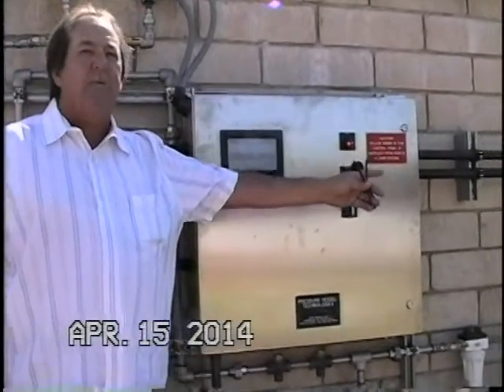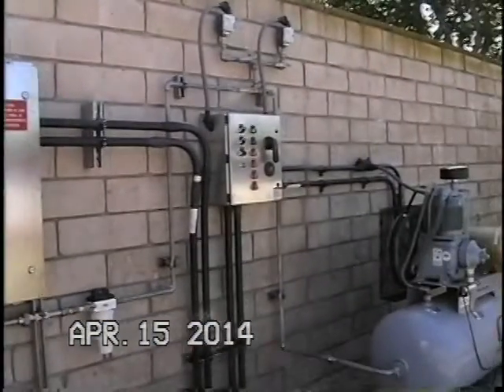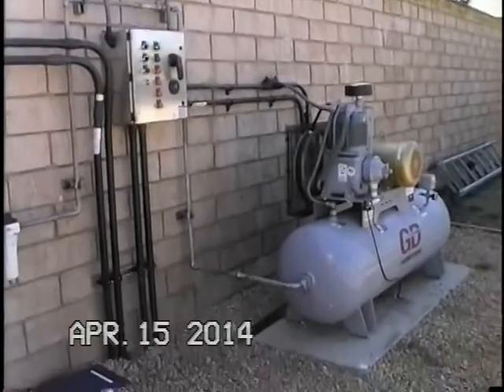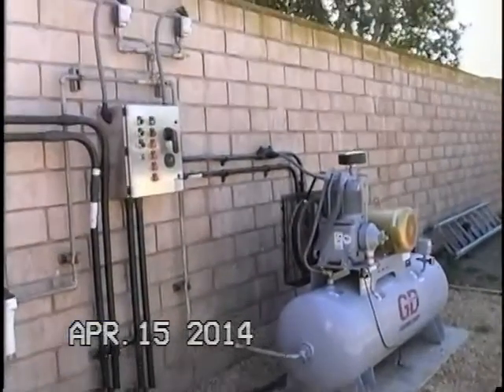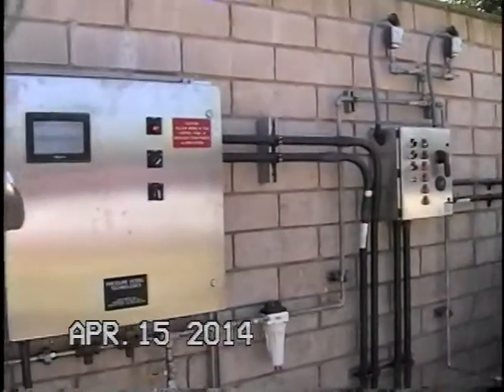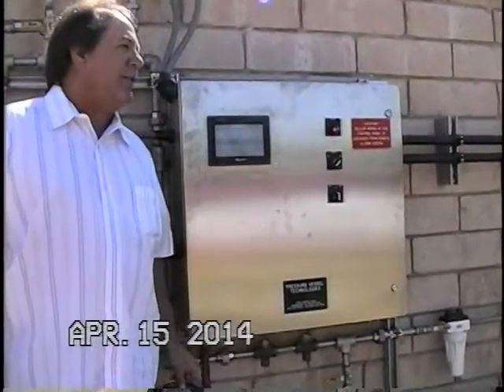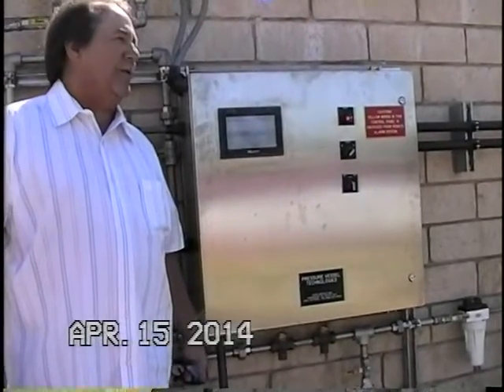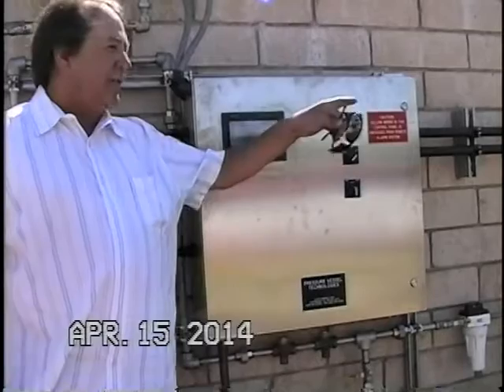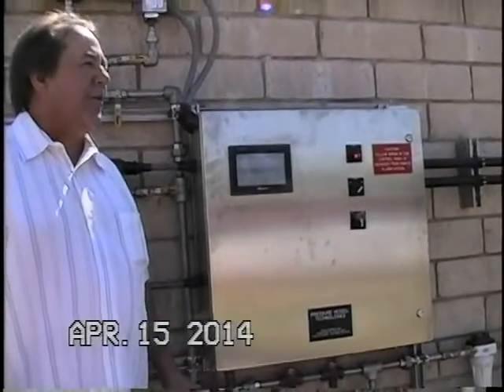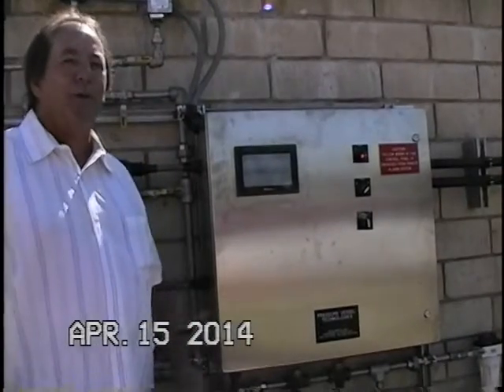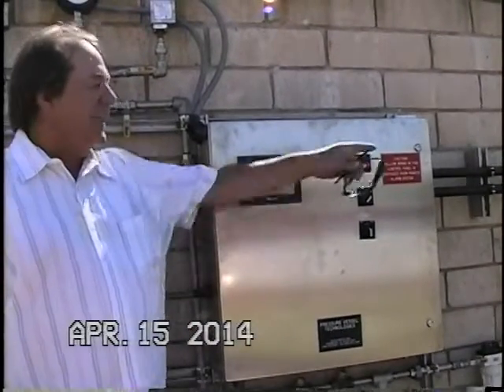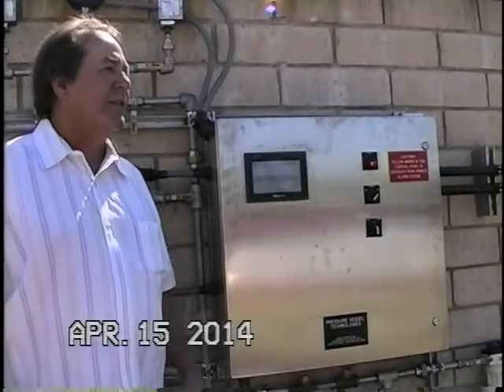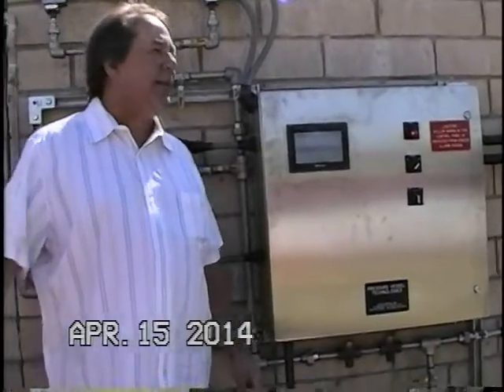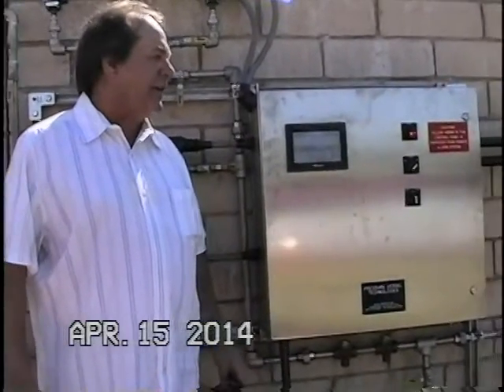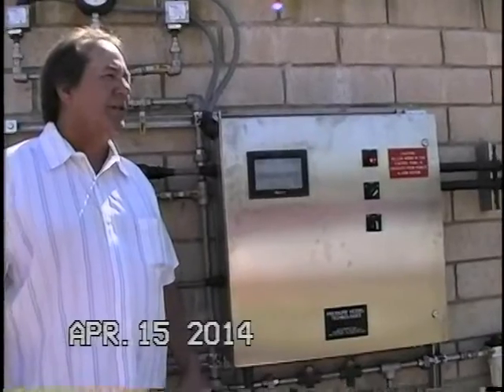These compressors are sized for air makeup. They're not sized for actually charging the initial charge of the surge tank. Now, you can, but as we found out, it's going to take about 5 to 6 hours to charge a tank that size with that compressor. So if you don't want to wait around 5 or 6 hours, I suggest you get a big portable compressor in here, charge it up to 120 and let it finish off. It's a good suggestion, especially if you take the system completely down. Now, it can charge it. I did it while we were here, but it certainly was a long time.